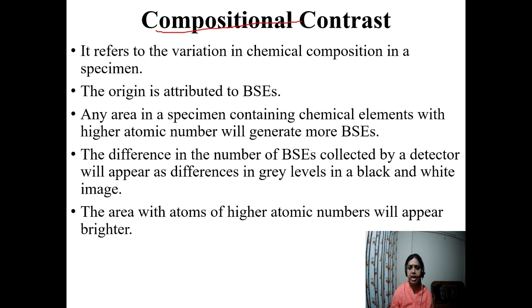Whenever we want to collect compositional contrast, how can we collect backscattered electrons? Just by changing the voltage to the Faraday cage, to the ET detector. The difference in the number of backscattered electrons collected by the detector will appear in gray scale, either in black and white. Suppose, as I just mentioned, copper and tungsten: if it is tungsten, it will look brighter. If it is copper, it will not look that bright. So just by the brightness scale, we can compare that these are two different atoms. Higher atomic number will appear bright. This is how we can distinguish what kind of elements are present.